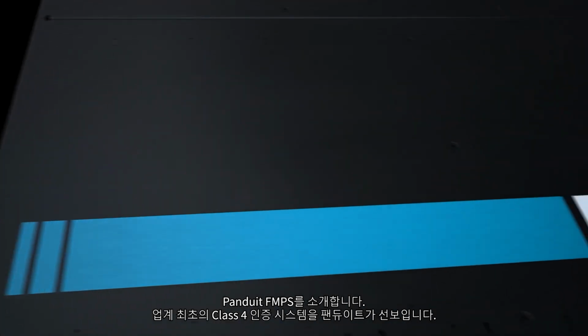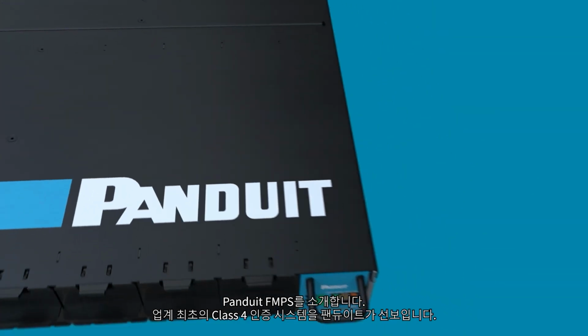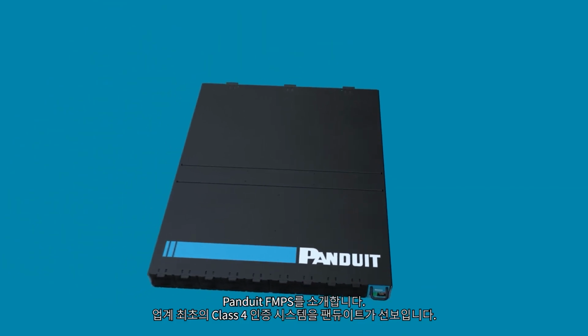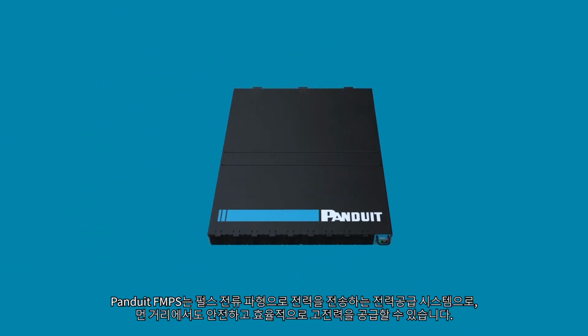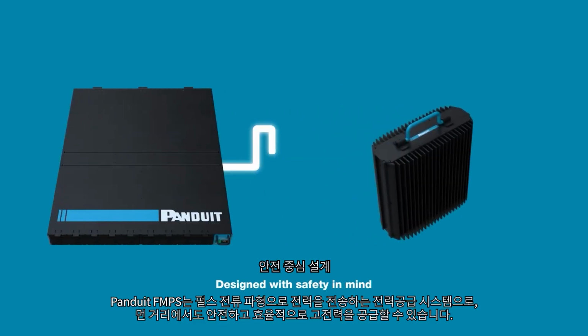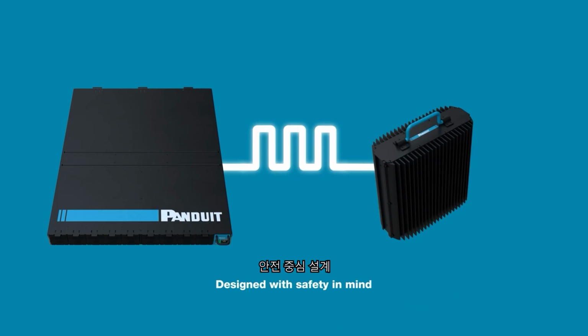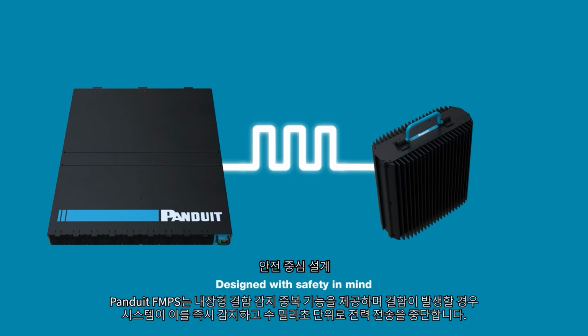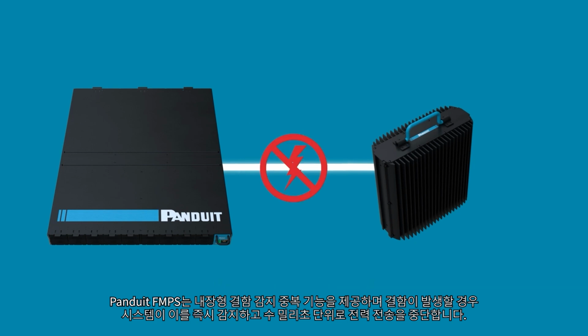This is the Panduit Fault Managed Power System, or FMPS, the first certified Class 4 system in the market, brought to you by Panduit. Panduit FMPS is a power delivery system that transports power in a pulse current waveform, which allows it to deliver significant power over long distance safely and efficiently. Panduit FMPS has built-in fault detection redundancy. If a fault occurs, the system will detect it and stop power transmission within milliseconds.